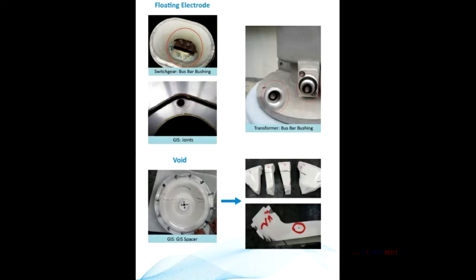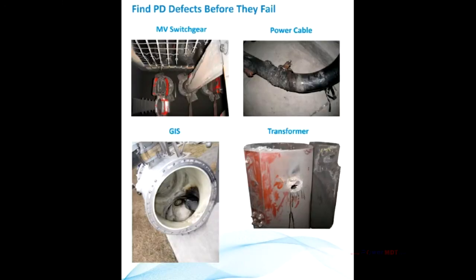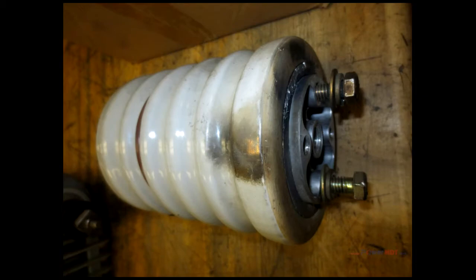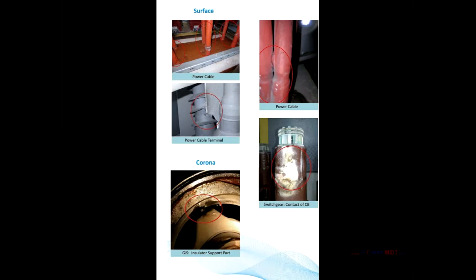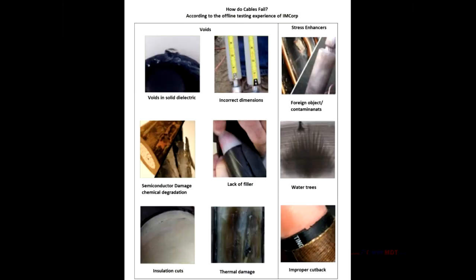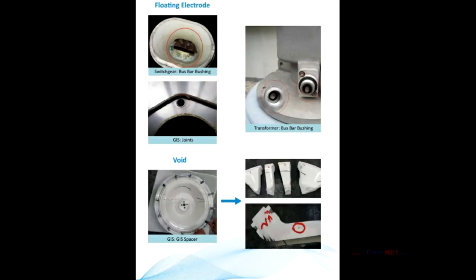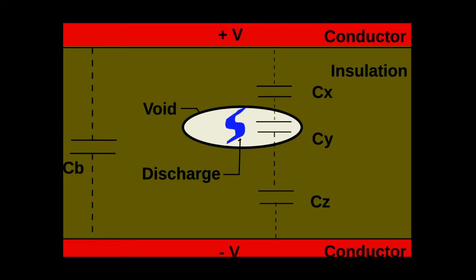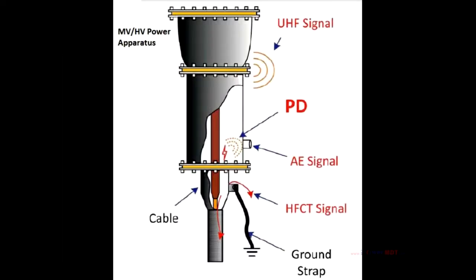Online PD testing detects and precisely locates insulation defects such as corona, surface tracking, arcing, voids, and floating electrodes. These issues are related to AC voltage stresses. In fact, partial discharges are completely driven by voltage and do not require a load or high current in order to become active.